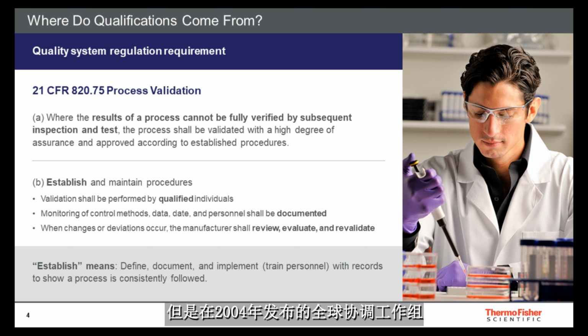But it is in the 2004 release of the Global Harmonization Task Force Process Validation Guidance document, which is an internationally harmonized document recognized by both the US FDA and ISO, that further clarifies the definition of IQ, OQ, and PQ, how it is applied, and establishes the qualification as the industry standard mechanism to document performance for medical devices.